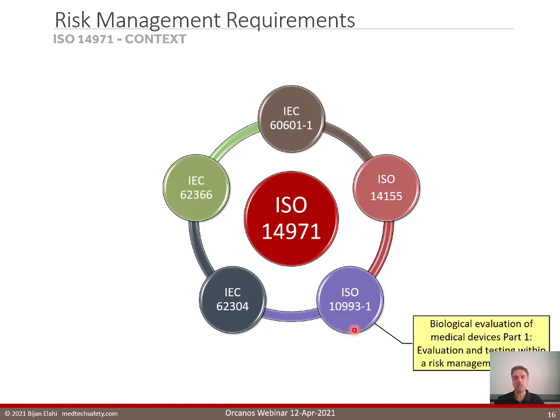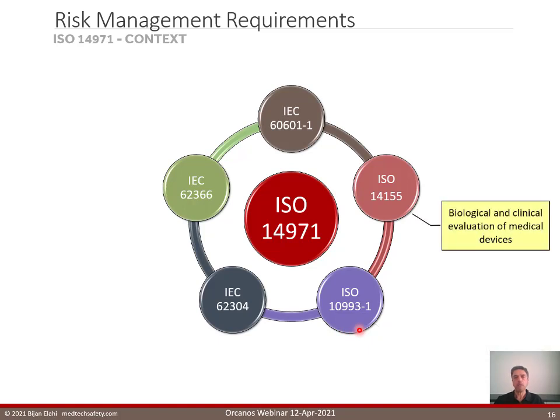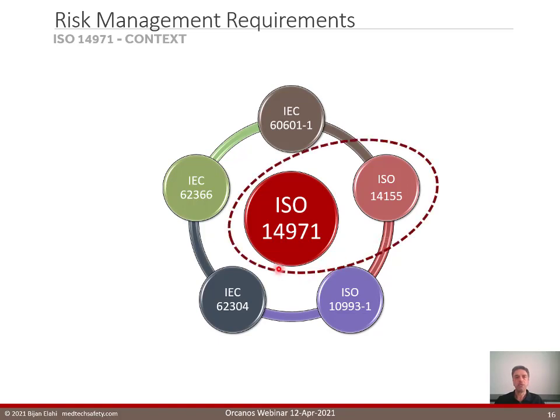If your medical device makes intimate contact with human tissue, then biocompatibility is a factor and you would be subject to ISO 10993-1. And if you do a clinical investigation of your medical device, you would be subject to ISO 14155. All of these standards make normative references to ISO 14971, and that means that they become one parcel. In other words, you cannot conform to ISO 14155 unless you also conform to ISO 14971.